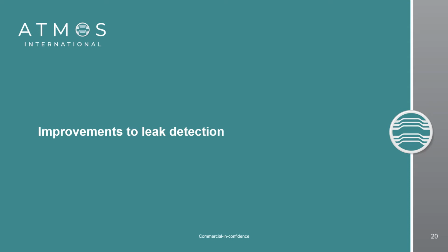the improvements that we have made to these leak detection systems? Well, I don't know how much you know about leak detection systems, but there's a number of papers out there that discuss the advantages and disadvantages that each method has. One of the biggest disadvantages a flow balance system had was that because it's utilizing SCADA rate data, and that could be at 1 second, 5 seconds, 15 seconds, it limits the leak location accuracy that you can provide, meaning the best case scenario for most flow balance technology would be ±1 kilometer. If you're doing theft detection with that, or even leak detection with that, that isn't good enough.